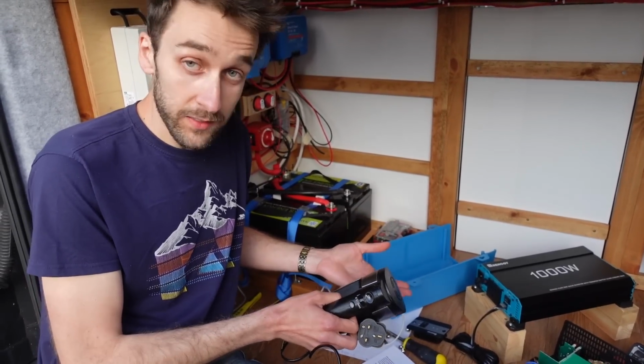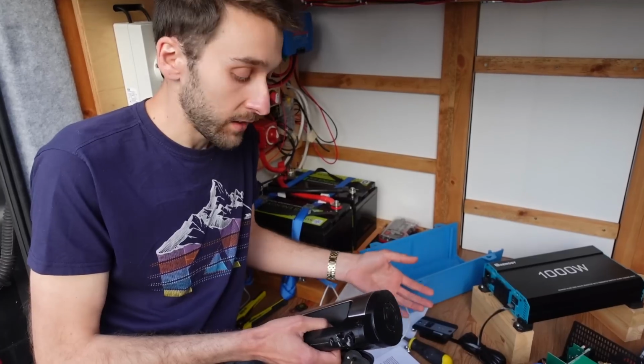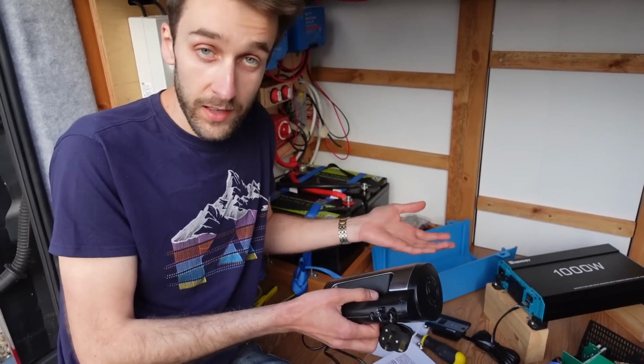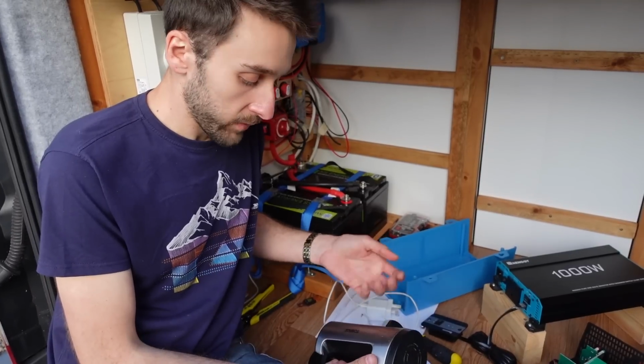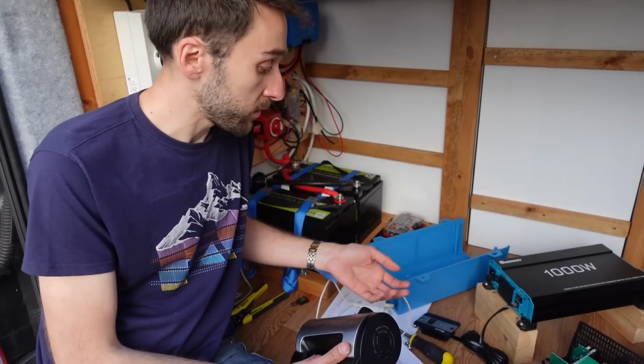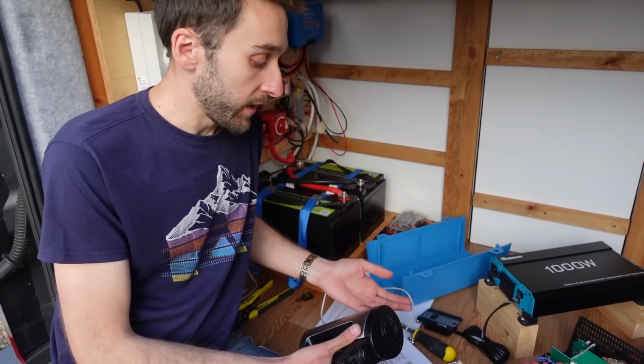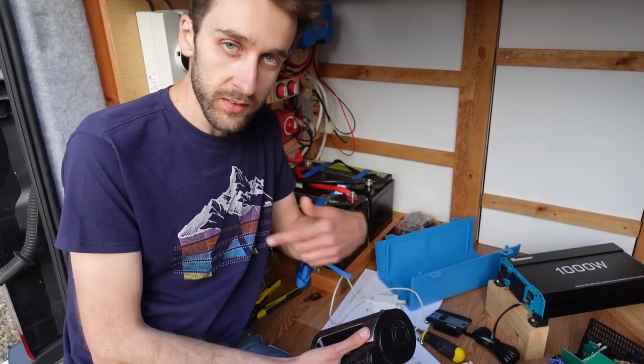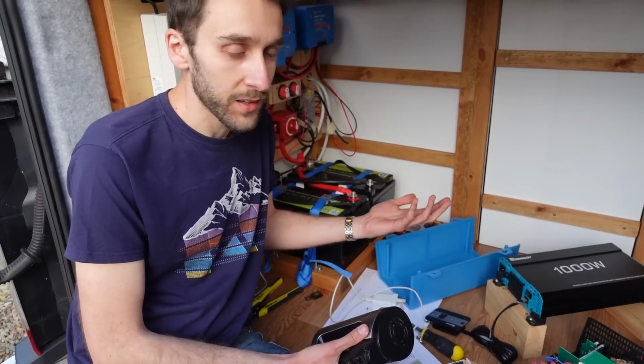The key thing is, if you then had a second device plugged in which was also class 1, and that had a fault too, you could be touching both at the same time - holding the kettle while touching a toaster, say - and if there was a fault scenario, it could complete the circuit and current would go through you, which would not be good.